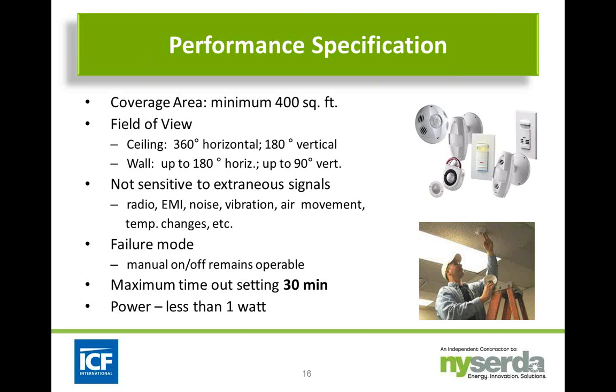Many of these devices have electronics that are operating at all times, even when they're in standby mode or if the lights are off. And this can actually create a vampire power situation where, if you have enough devices in the building, you can add thousands of watts to the operation of the building by adding your occupancy sensors. In general, the savings you're going to garner from using occupancy sensors is going to far outweigh what you're going to lose from your vampire power, but you want to make sure that that standby power stays below 1 watt.